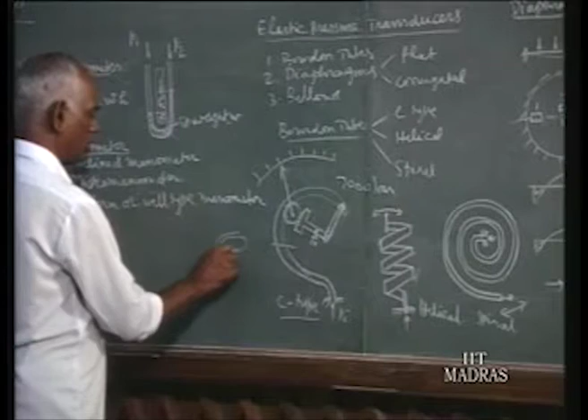That free end motion is taken by linkages and given to a rack and pinion mechanism, with a lever mechanism pivoted here. The pinion axis is given to a pointer which moves over a calibrated scale. To measure higher pressure, the thickness is increased, and the cross section gets nearer to circular. For very high pressures the ovality is small, and when ovality is reduced, the amount of deflection is reduced. To compensate for this, people go for helical or spiral type Bourdon tubes.